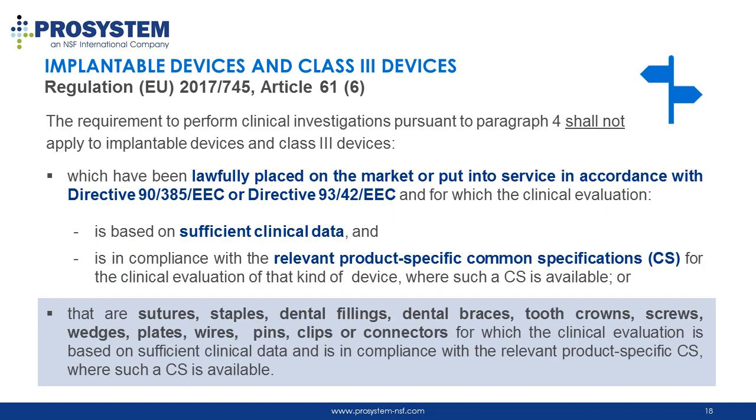In paragraph 6, it is also stated that the requirement to perform clinical investigations does not apply to implantable devices and class 3 devices which have been lawfully placed on the market and put into service in accordance with the directives, as well as if they belong to product types such as sutures, staples, dental fillings, dental braces, tooth crowns, screws, wedges, plates, wires, pins, clips, or connectors.